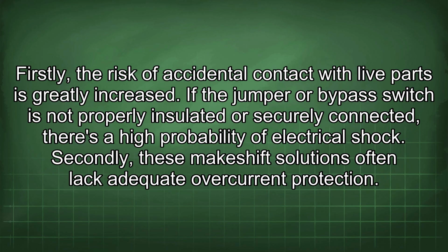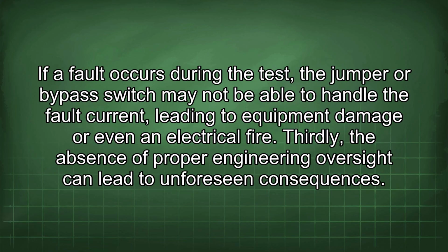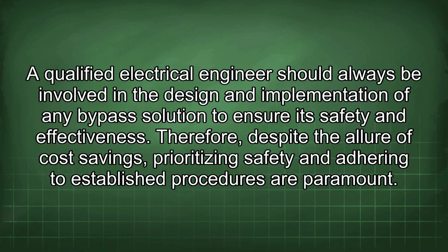Secondly, these makeshift solutions often lack adequate overcurrent protection. If a fault occurs during the test, the jumper or bypass switch may not be able to handle the fault current, leading to equipment damage or even an electrical fire. Thirdly, the absence of proper engineering oversight can lead to unforeseen consequences. A qualified electrical engineer should always be involved in the design and implementation of any bypass solution to ensure its safety and effectiveness.